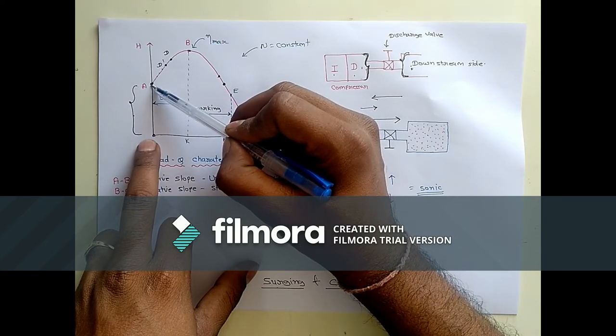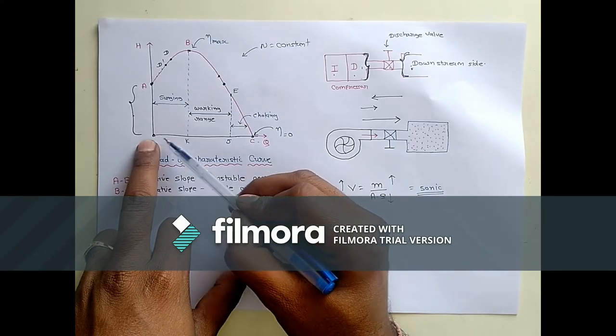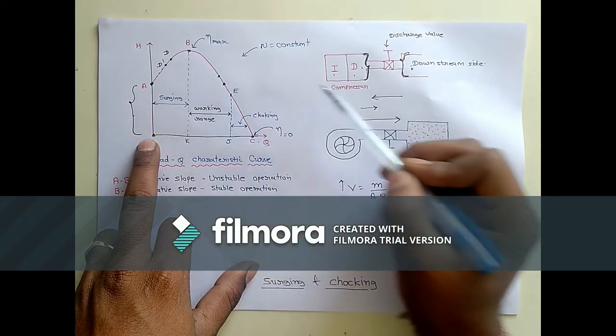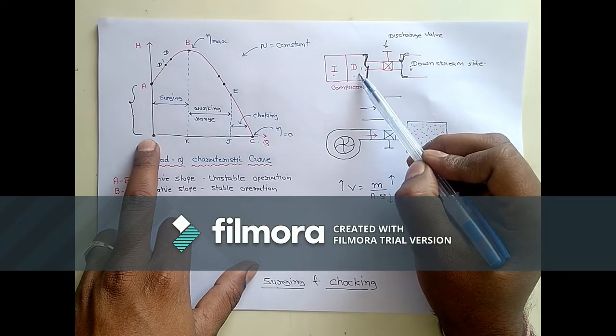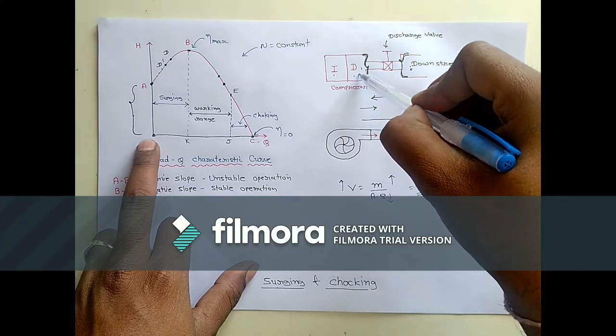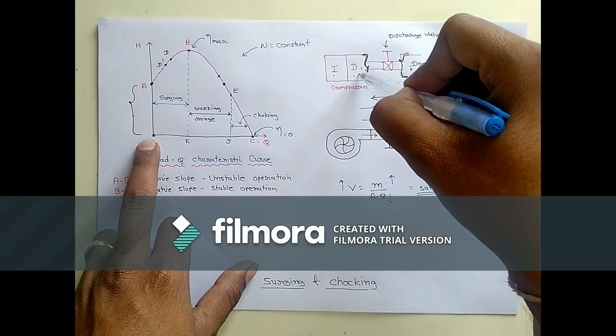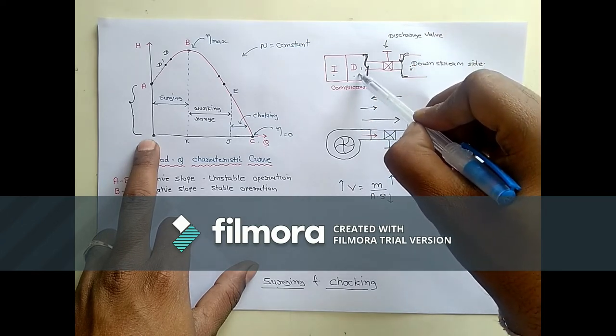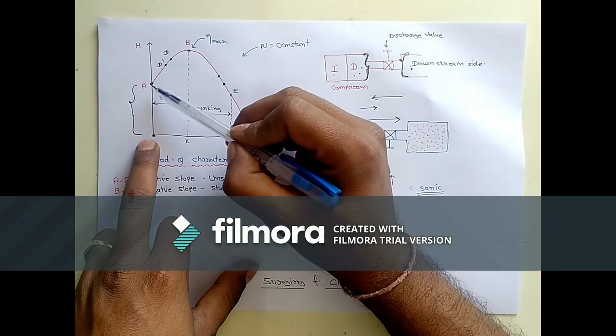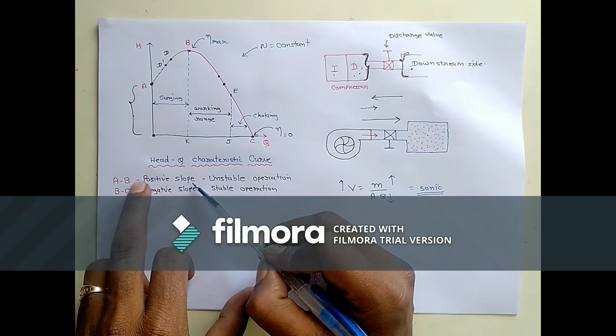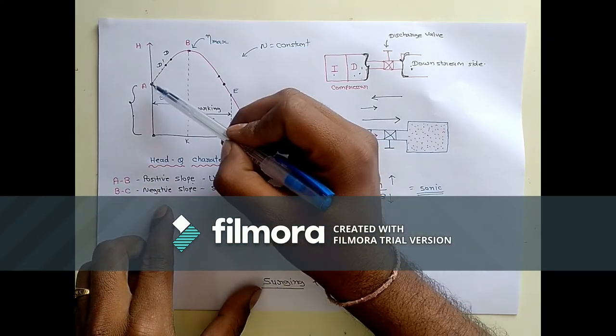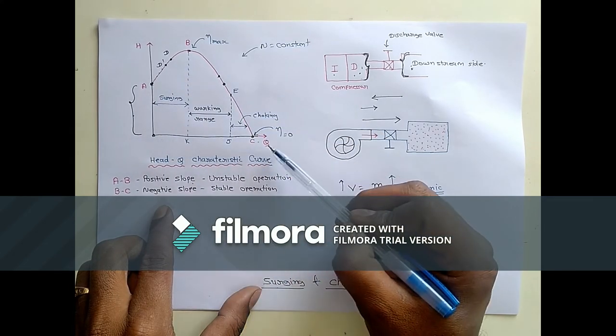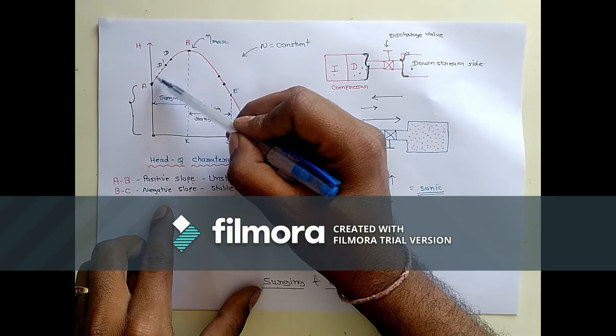As the discharge increases from this point to this point, the head also increases. That is due to the diffusion action in the diffuser. The function of the diffuser is to convert the kinetic energy given by the impeller into pressure energy in the diffuser section. From A to B this is a positive slope and it is generally unstable operation. During A to B the pressure gradually increases with respect to discharge.